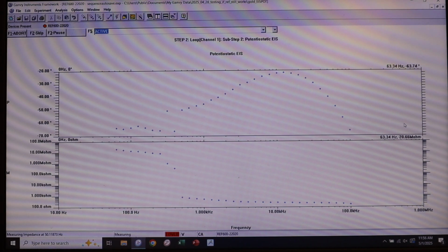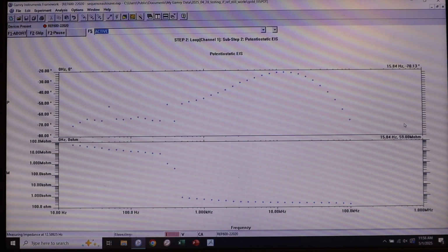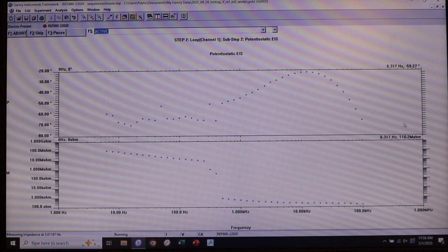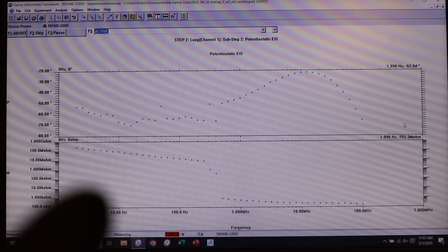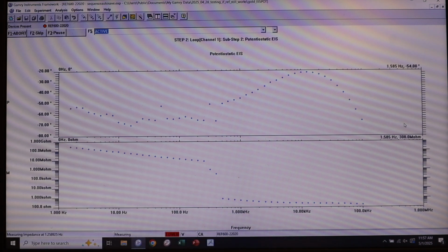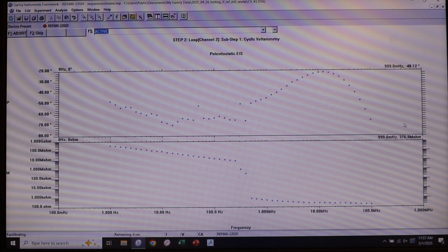So now you can see there's this flashing red light here on the bottom of our screen, and we can see that there's a huge discontinuity where we were looking at really low impedance measurements here, and all of a sudden now it's just terrible measurements. And so this is the first sign that, hey, maybe something is wrong.